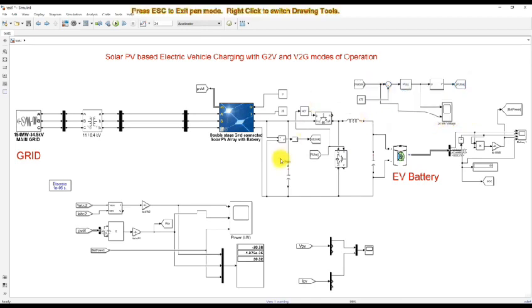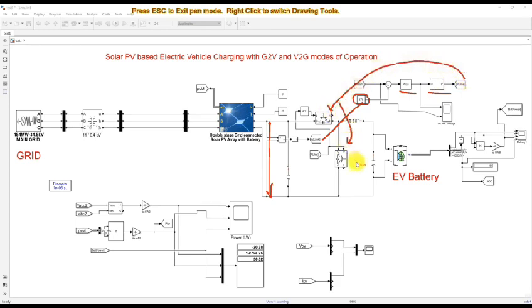Here we measure the DC link voltage, which is compared with the reference voltage. We maintain the DC link voltage around 470 volt. It is compared with 470, processed via a PI controller, and then processed via a PWM generator. The PWM generator generates the pulse, which controls the IGBT of the bidirectional DC-DC converter.